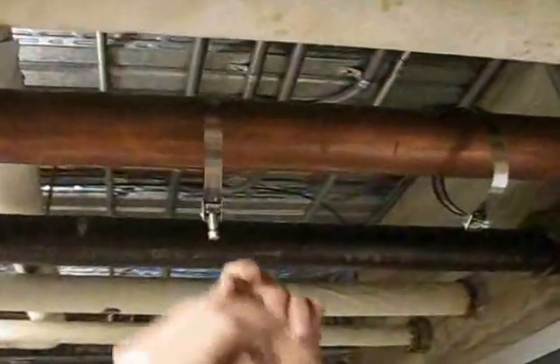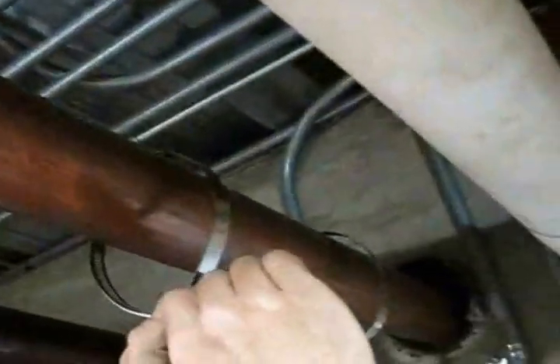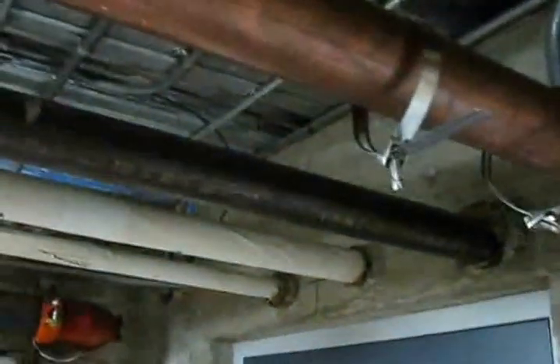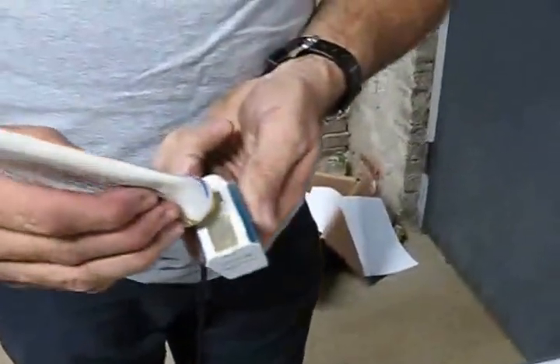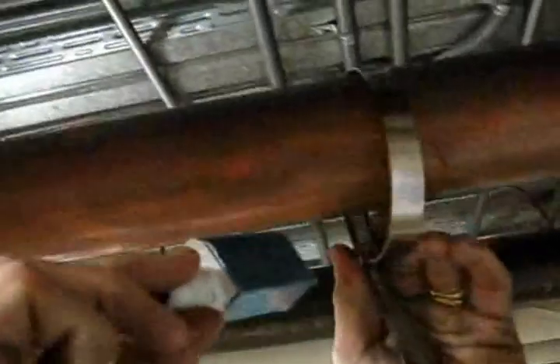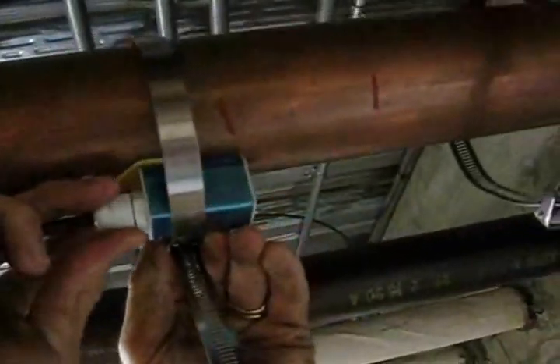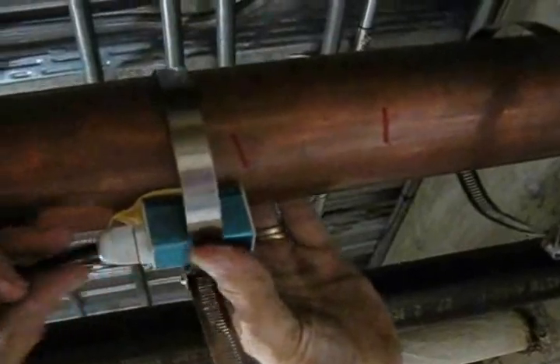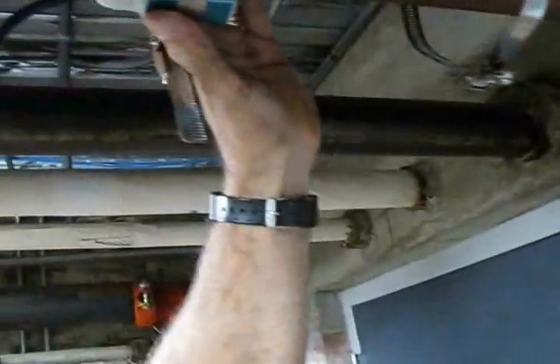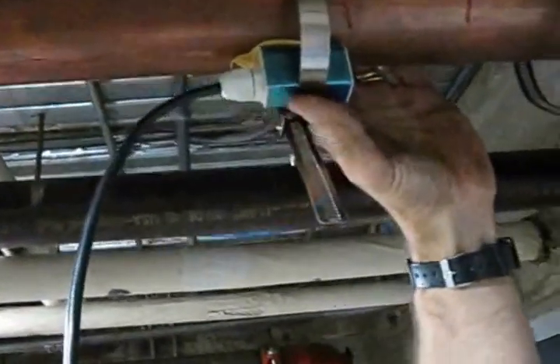Next is to apply the clamps to the pipe. What you want to do is get the clamp on and tighten it up to a certain point, but still allow room to slide the transducer back and forth. Your next step is to apply a couplant to the transducer. You place the transducer with the clamp with the wires out. At this point, the transducer should sit in the proximity of the marks you have made on the pipe. At this point, you can tighten the clamp to ensure proper contact.